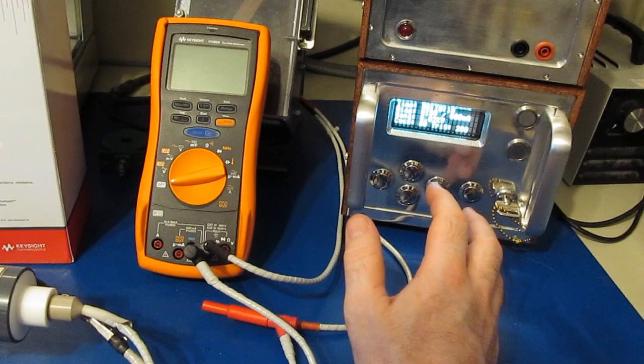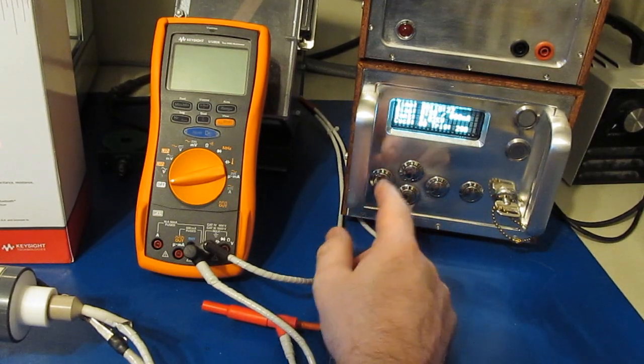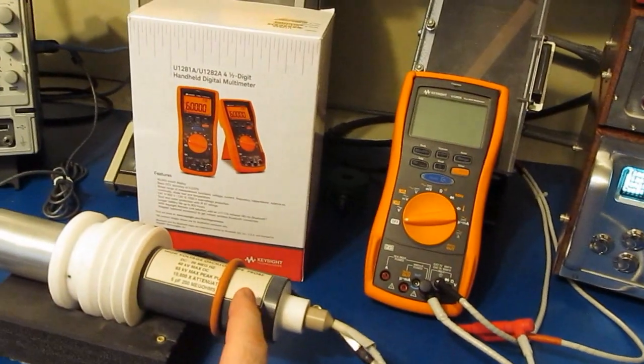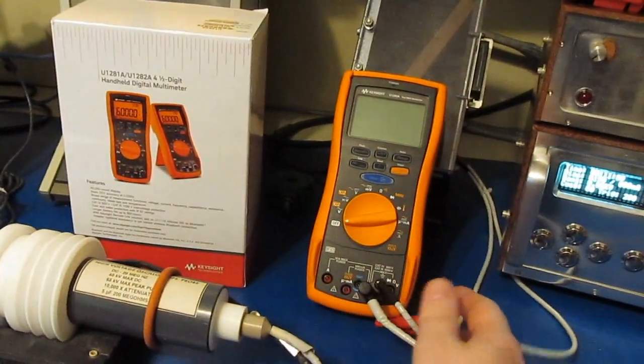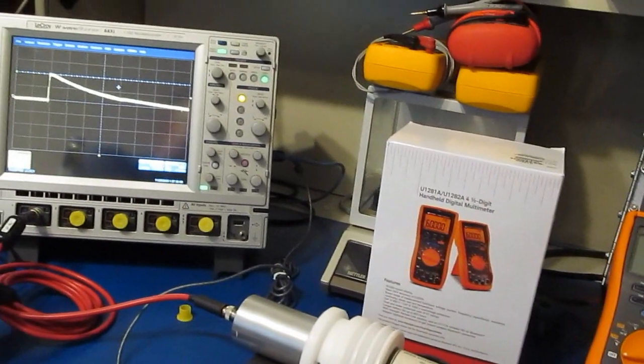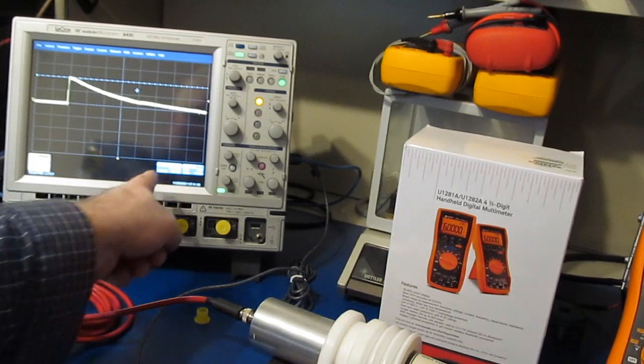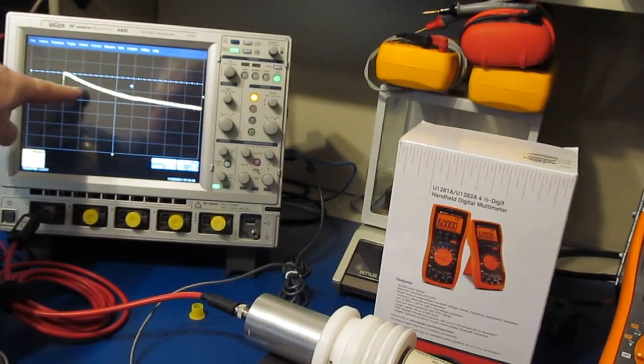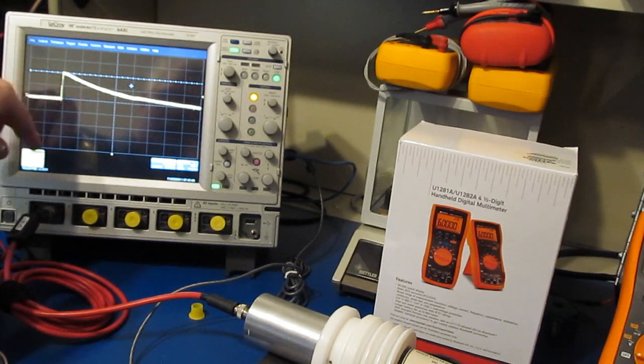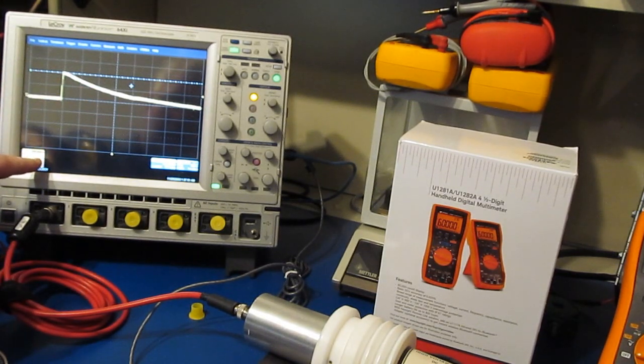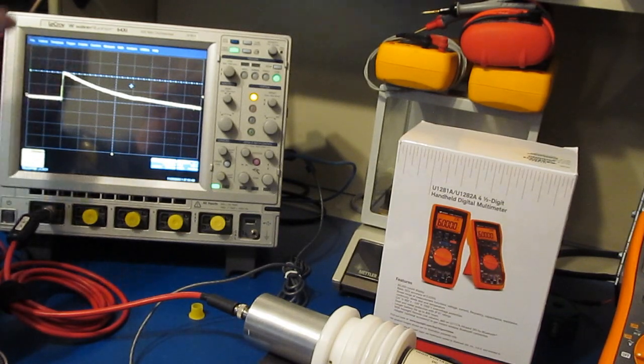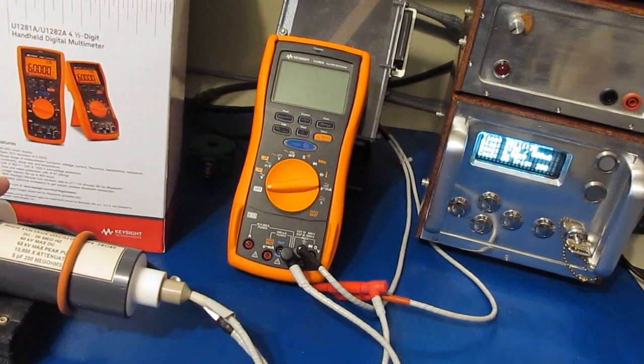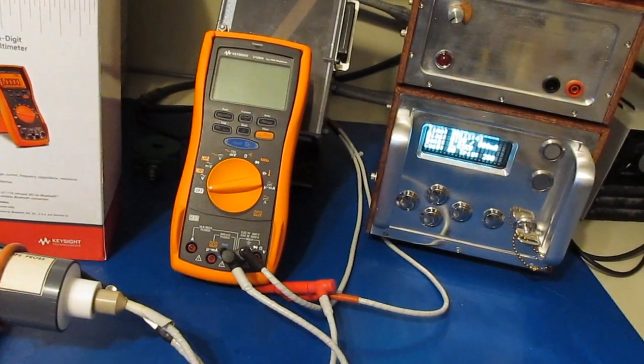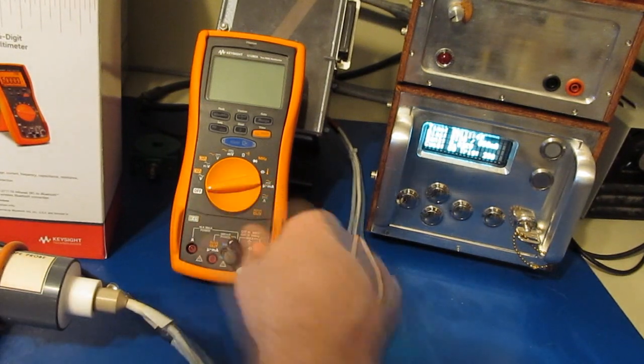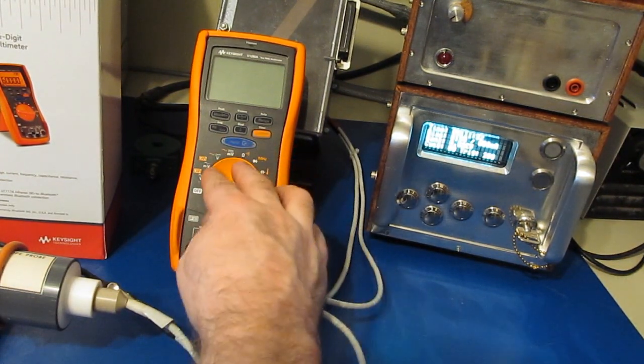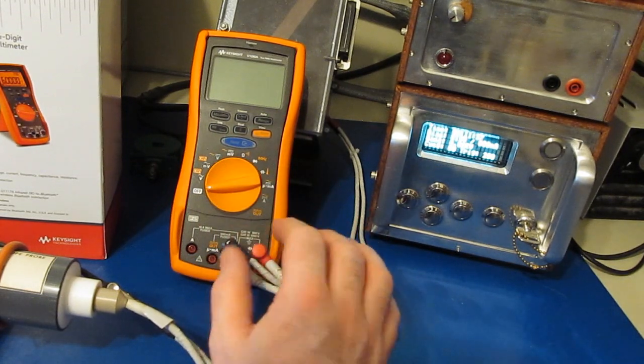Next, we're going to transient test the U1282A. Again, we'll be using the smaller transient generator. On my left here, you can see I have our high voltage probe. This will be attached right to the leads of the meter, and this is attached to our oscilloscope. The oscilloscope is currently set for 50 microseconds per division. You can see halfway up we're 2 divisions out, or 100 microseconds. It's set for 500 volts per division. It is currently 2 divisions up, or 1000 volts peak. Again, I use this high voltage probe with the oscilloscope to monitor when the meter starts to break down. Again, we'll be applying 5 transients, both positive and negative, with the meter set to each mode. And again, we'll be flipping the leads to change the polarity.